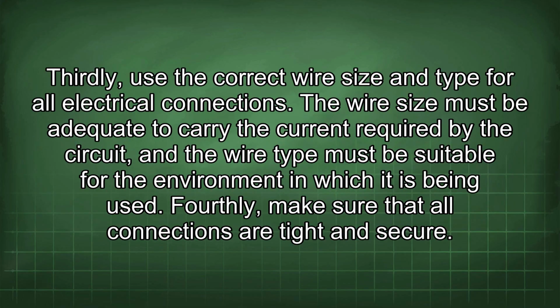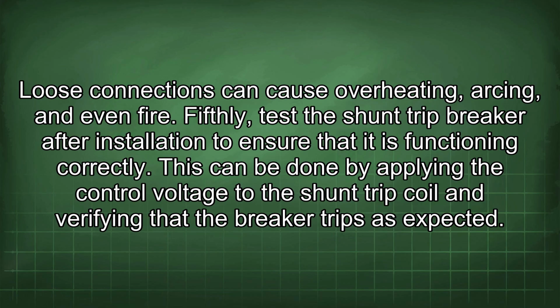Thirdly, use the correct wire size and type for all electrical connections. The wire size must be adequate to carry the current required by the circuit, and the wire type must be suitable for the environment in which it is being used. Fourthly, make sure that all connections are tight and secure. Loose connections can cause overheating, arcing, and even fire. Fifthly, test the shunt trip breaker after installation to ensure that it is functioning correctly. This can be done by applying the control voltage to the shunt trip coil and verifying that the breaker trips as expected.